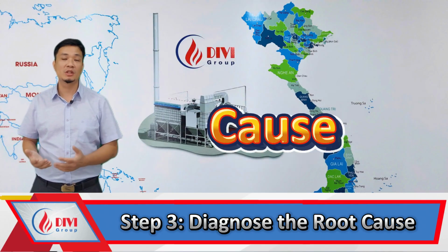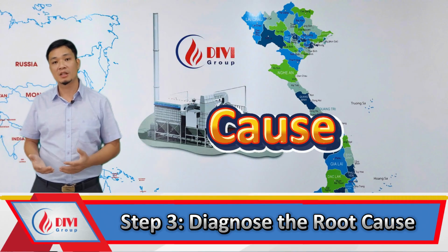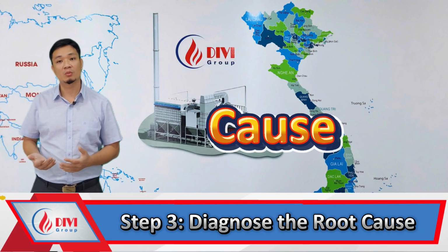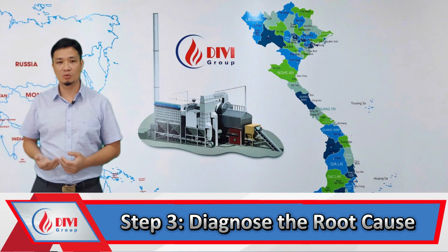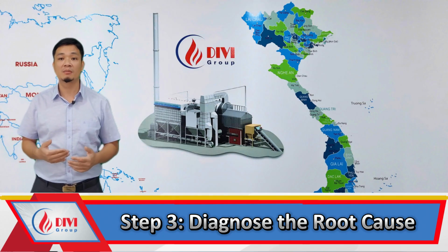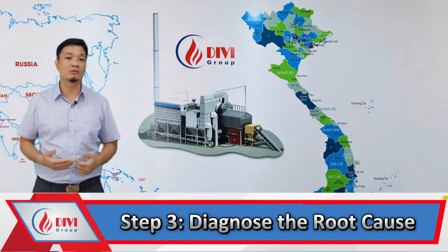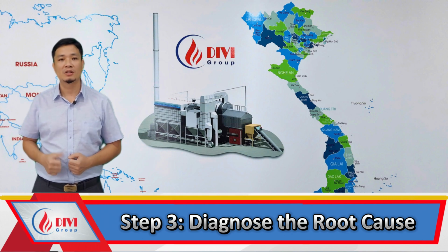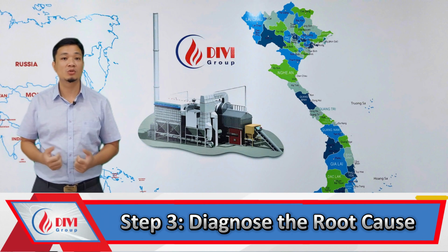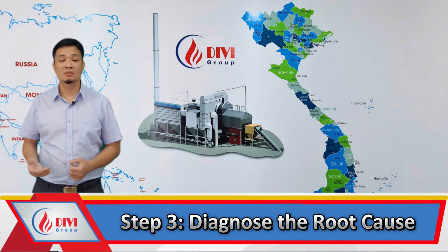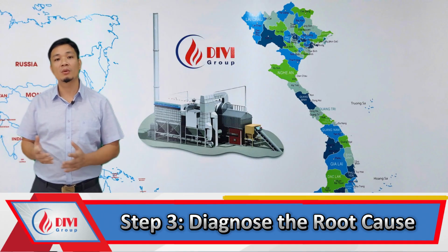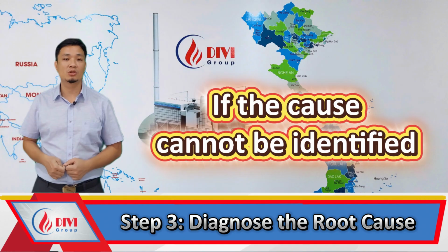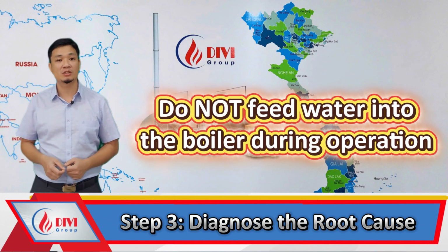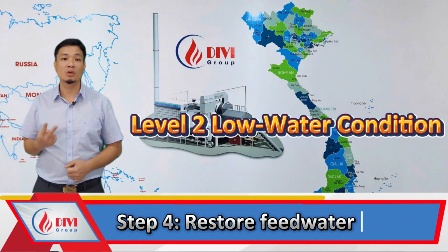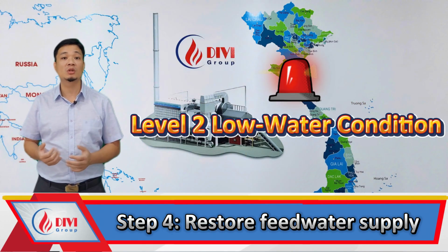It is absolutely essential to identify and completely resolve all causes of the water loss before attempting to refill the boiler. If you skip this step and rush to refill water without a full assessment, it may cause additional damage or even trigger a boiler failure. Never resume water supply or boiler operation unless the underlying issue that caused the second-level low water alarm has been properly addressed and corrected. Refill the boiler only after the issue is resolved.